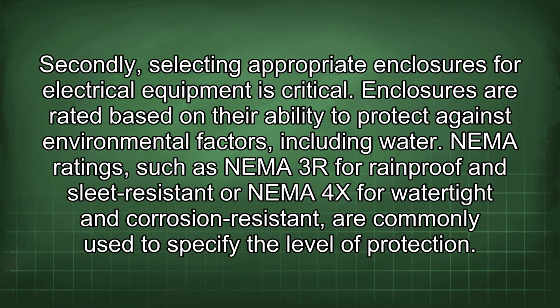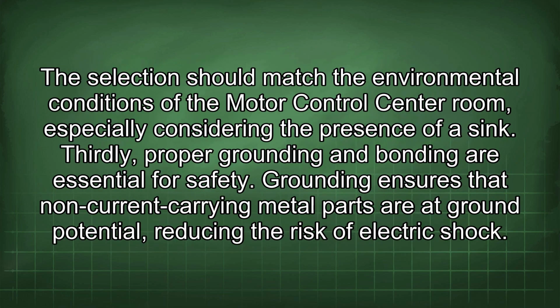Secondly, selecting appropriate enclosures for electrical equipment is critical. Enclosures are rated based on their ability to protect against environmental factors, including water. NEMA ratings, such as NEMA 3R for rainproof and sleet resistant or NEMA 4X for watertight and corrosion resistant, are commonly used to specify the level of protection. The selection should match the environmental conditions of the motor control center room, especially considering the presence of a sink.